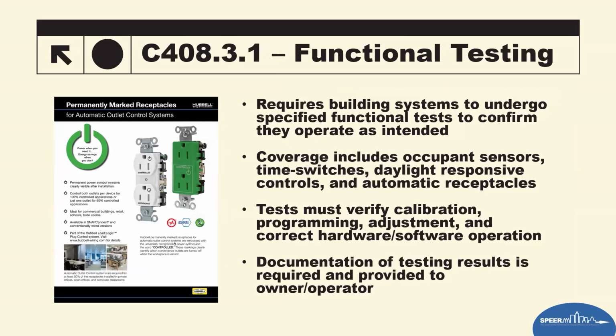We just mentioned this term, functional testing, which is now a section here. Basically, it mandates that key control systems, not just equipment, also need to function and be tested. That's lighting controls, occupant sensors, time switches, daylight response controls, automatic receptacles. These things now must also be commissioned. So verifying that all of these are programmed correctly on a schedule and also function as intended, like occupant sensors. These tests must be documented. The results must be included in the commissioning report. Basically, this ensures that they are actually designed and specified and meet the requirement of what was said to be specified on the planning report.